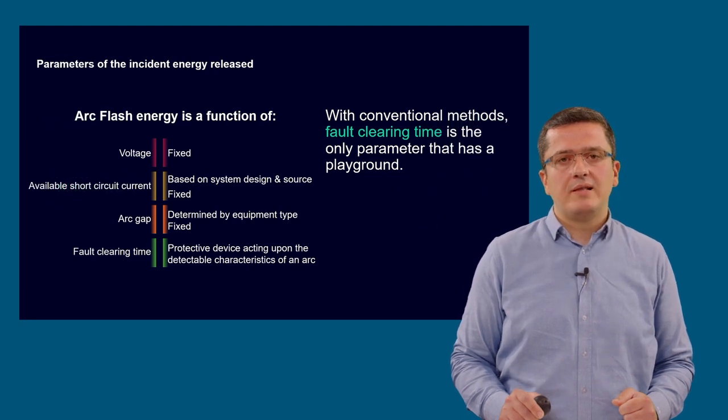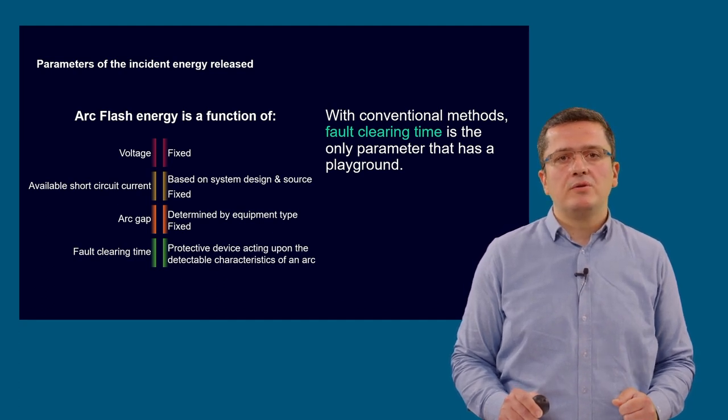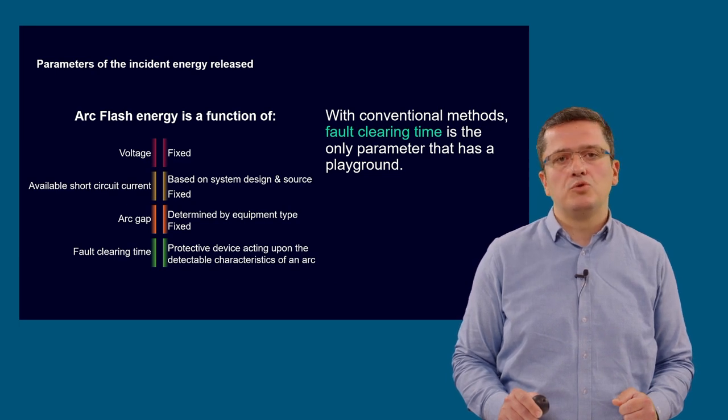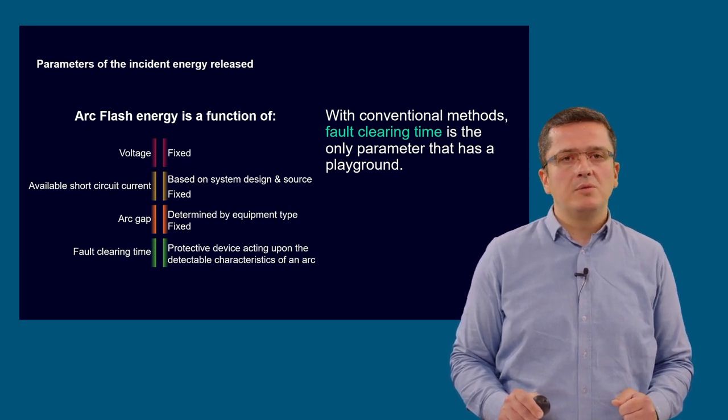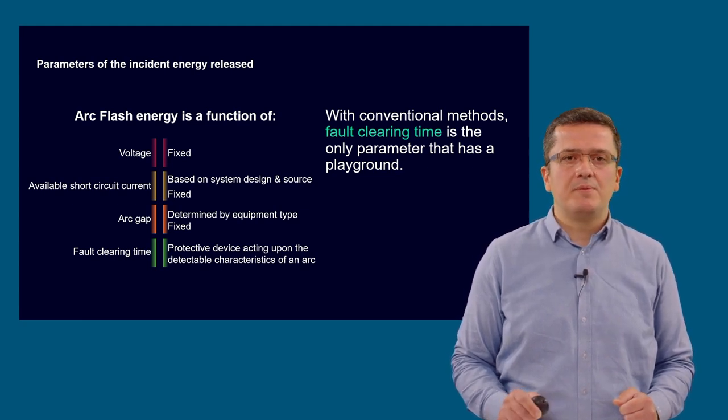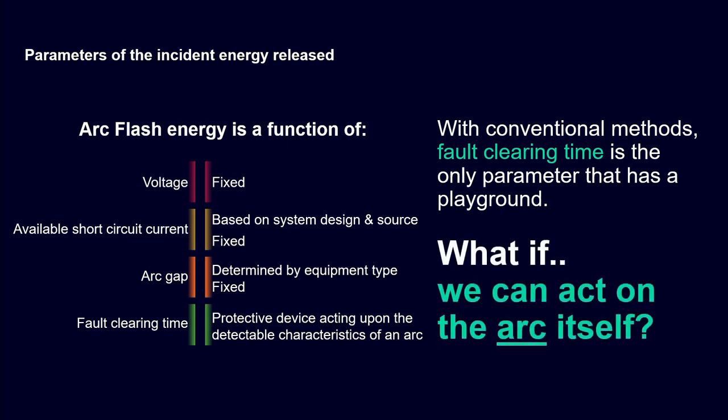Within this dilemma, there are some parameters already fixed without room for adjustment. In regard to limiting the arc flash incident energy, there is also not much room to play. Amongst the parameters, it is the fault clearing time we can act on by utilizing fast tripping circuit breakers and early detection of arc via light or pressure sensors. What if we would have the chance to act directly on the arc itself?